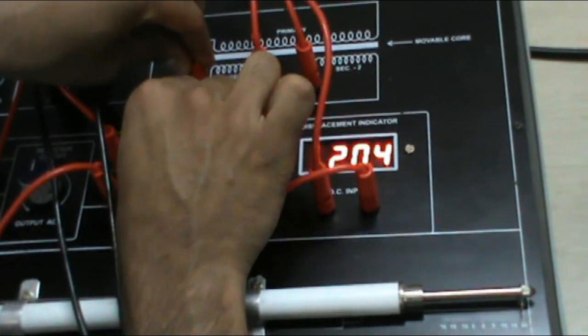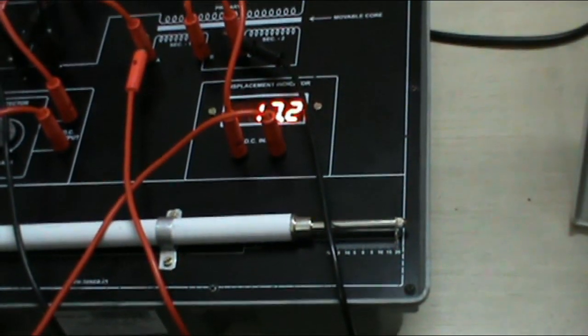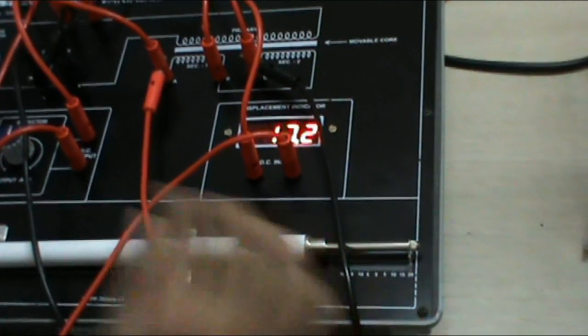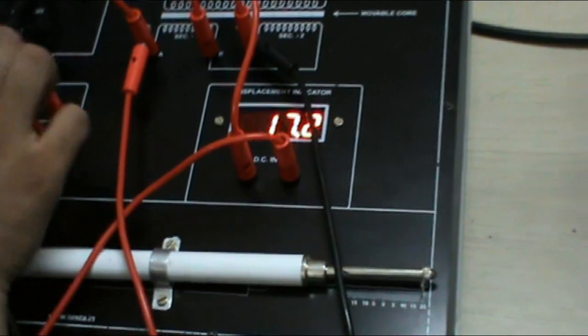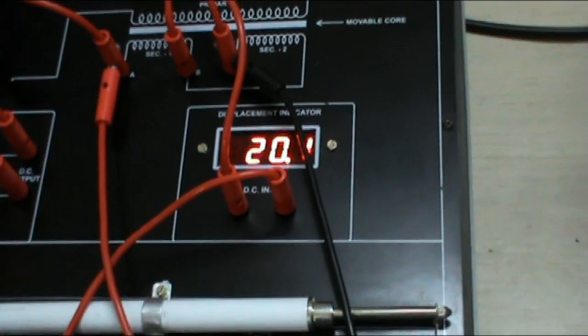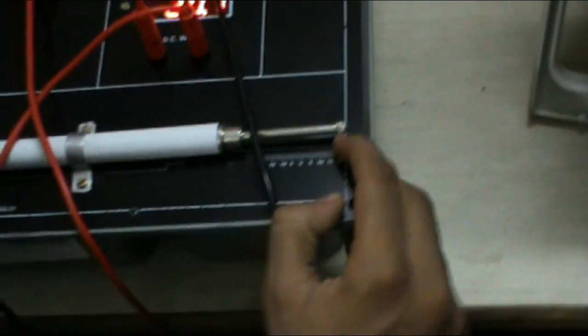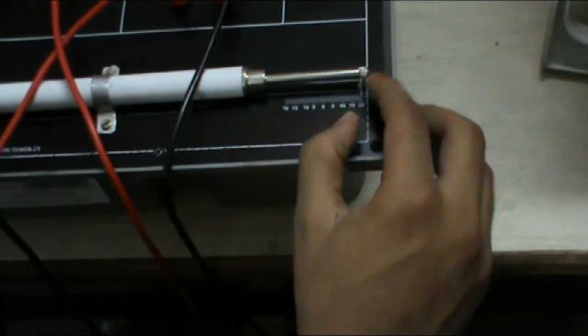Now to see the output, I connect channel 2 with this A and black lead to C. Now as we displace it from 20 to 0 to minus 20mm, the displacement can be seen in this indicator.